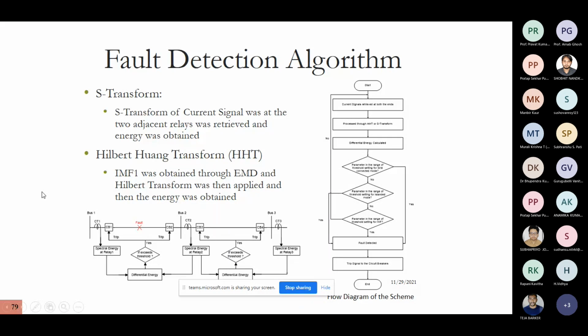And you are making a differential based protection, which is a very simple fundamental based protection. But is it adequate? If you take the simple current based approach and try to understand when you are taking a CT saturation, although at a distribution level, the question arises how the saturation of the CT really occurs.